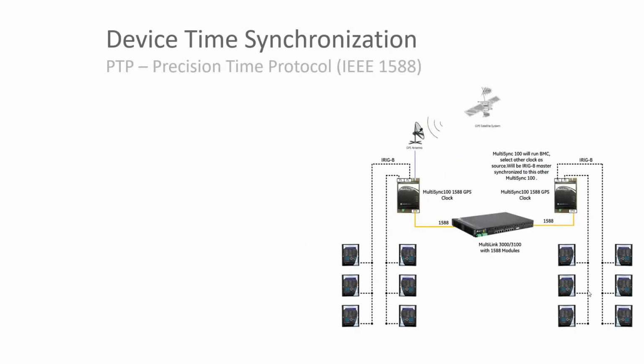That's where IEEE 1588 PTP, Precision Time Protocol, comes in, providing that accuracy, less than microsecond, even down to 100 nanosecond accuracy. Like NTP and SNTP, it uses the network to supply the clock signal, but is much more accurate, and can be used for synchrophasors, process bus, and any time-critical accuracy requirements.